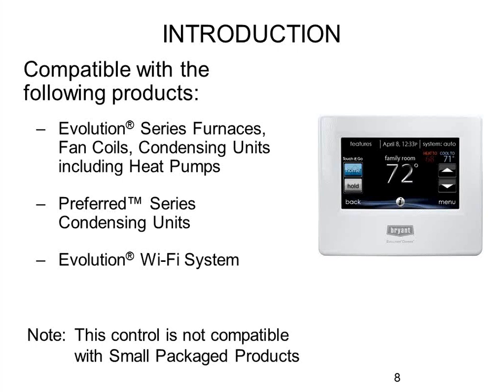The stat is also compatible with everything else you use with Evolution — ERVs, humidifiers, UV lights, and Evolution zoning systems. In fact, this touch screen Connex thermostat uses the same SKU for both zoning and non-zoning systems. Previously there were two versions of the Evolution stat — one for single zone and one for zoning with a 'Z' in the part number. That's no longer the case. When you plug this stat in and it scans, it'll also scan for a zoning board — if it finds one, it configures it; if not, it assumes single zone.